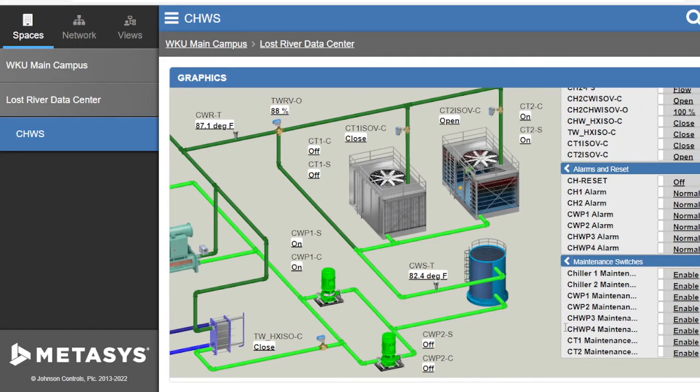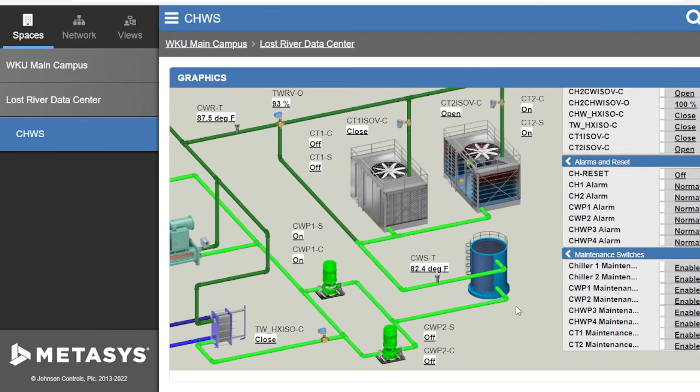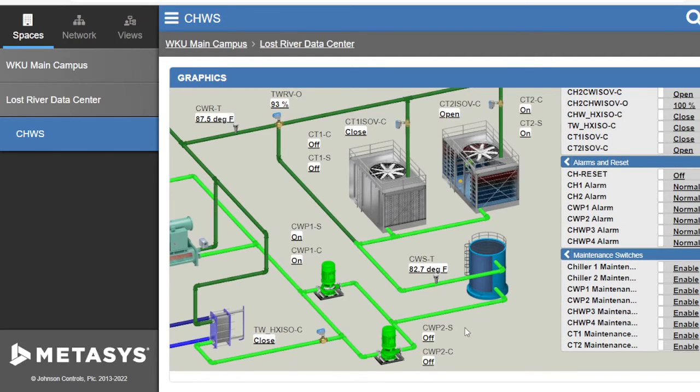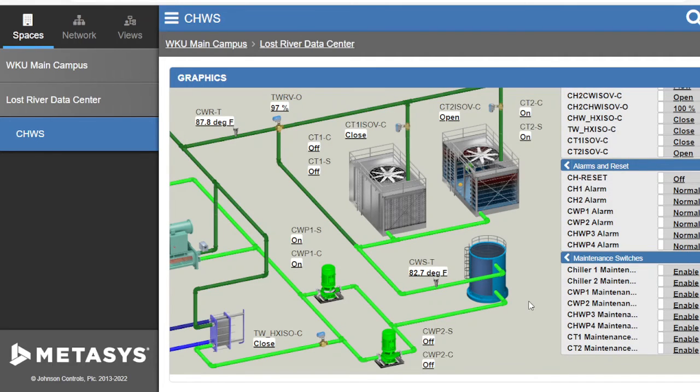And this is one of those situations where, having that maintenance switch and having the lead lag, once that service is done and you re-enable that maintenance switch, even if the opposite pump is in lead, what will happen is if there is a pump failure or that sort of thing, it will automatically switch over to the other pump regardless of what the lead is. Of course, it will generate an alarm, but at the same time, your system hopefully will stay online. But having the ability to switch over is very handy, guys.